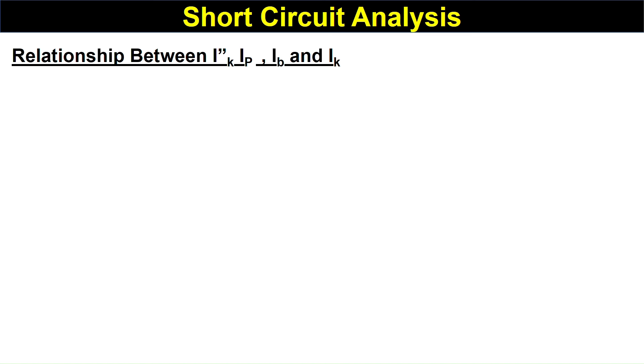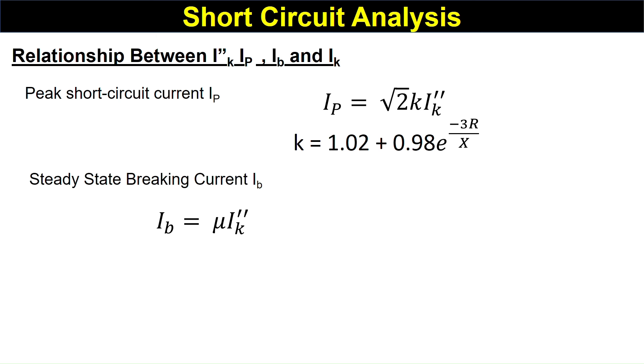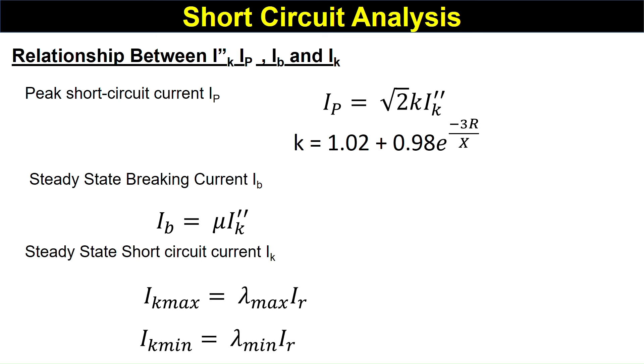There are certain relationships between the short-circuit current terms. The Peak Short-Circuit Current Ip equals √2 · k · I″k, where I″k is the Initial Symmetrical Short-Circuit Current and k depends on the R/X ratio. The breaking current IB equals μ · I″k, where μ is obtained from IEC 60909 tables. The Steady-State Short-Circuit Current Ik can be found as λmax · IR or λmin · IR, where λmax and λmin values are also from the IEC 60909 tables.